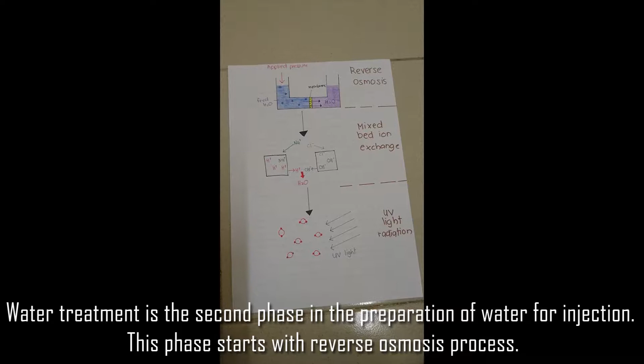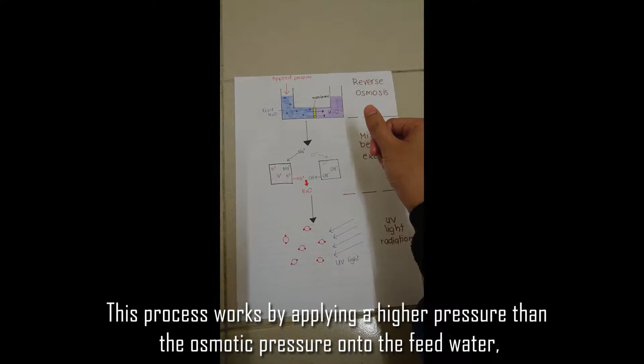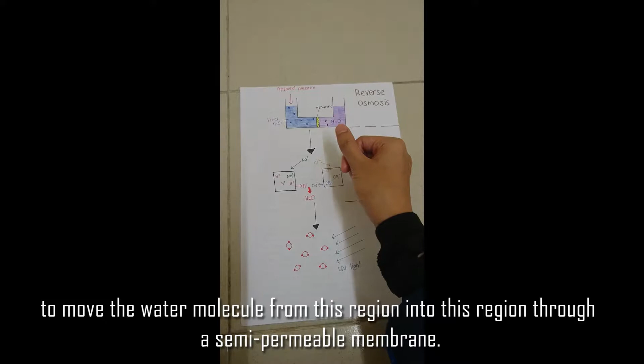Water treatment is the second phase in the preparation of water for injection. This phase starts with the reverse osmosis process, which works by applying a pressure higher than the osmotic pressure onto the feed water, moving water molecules through a semi-permeable membrane from one region into another.